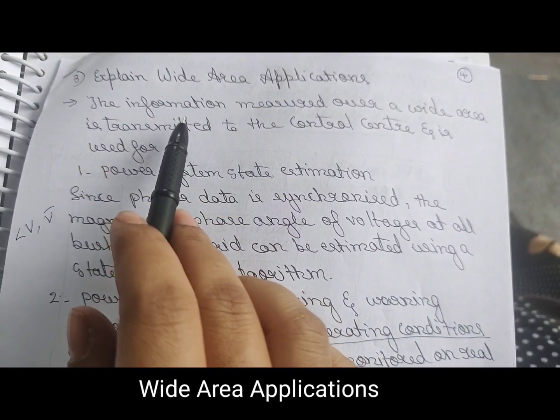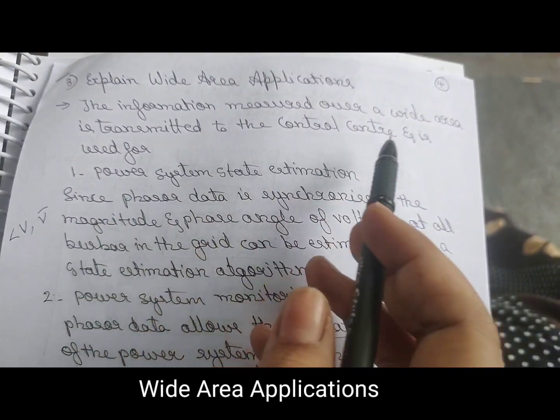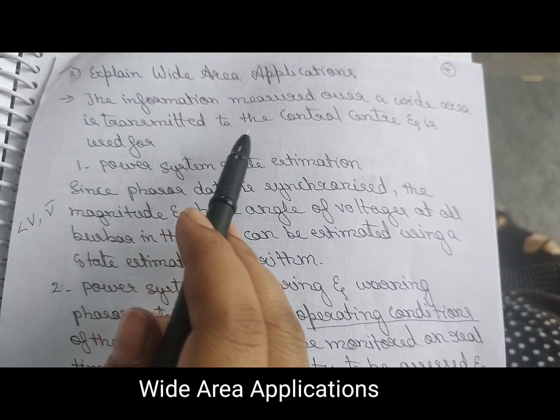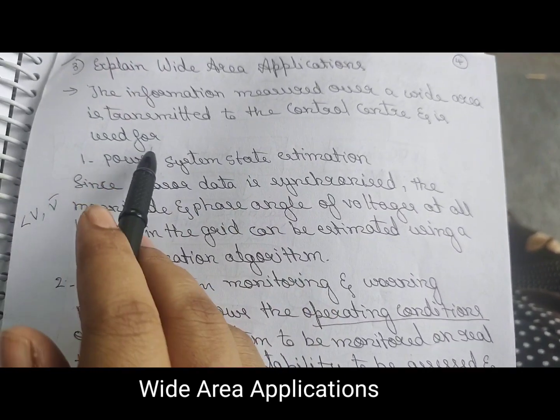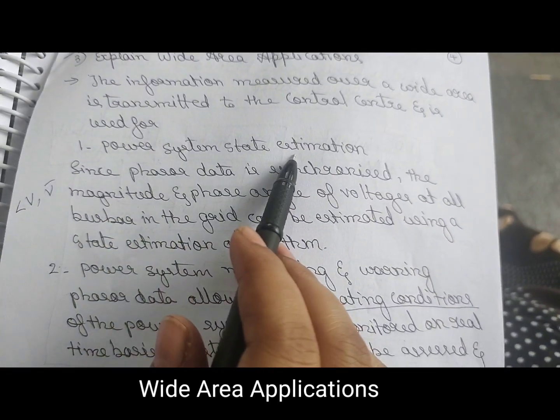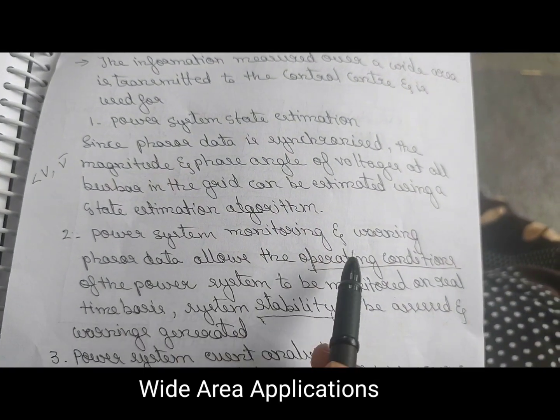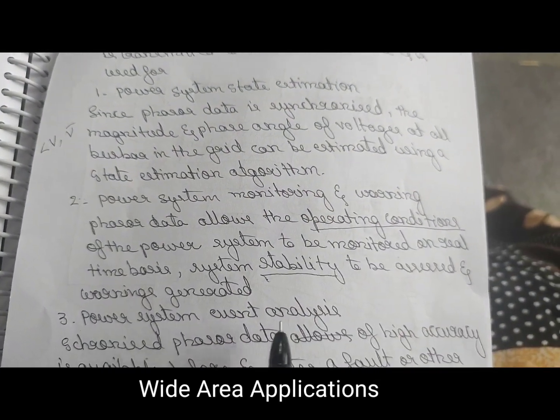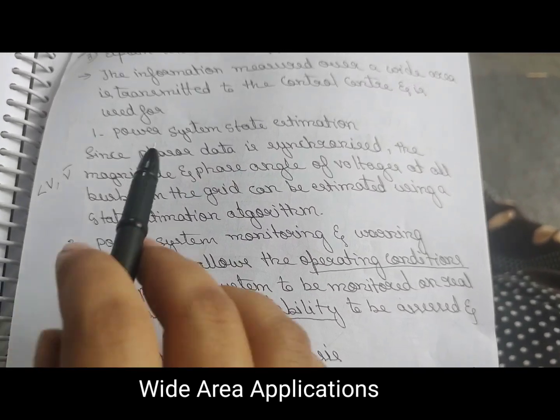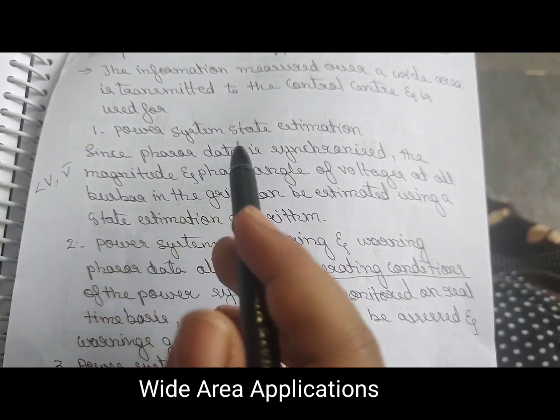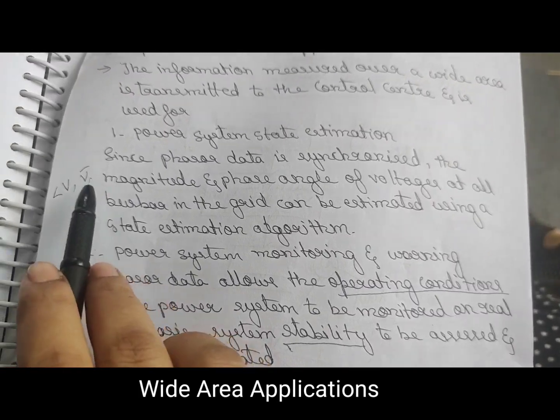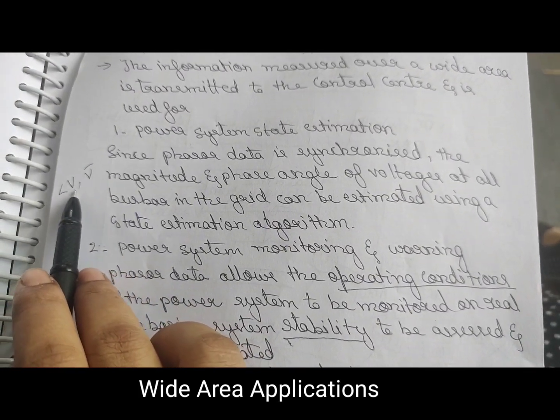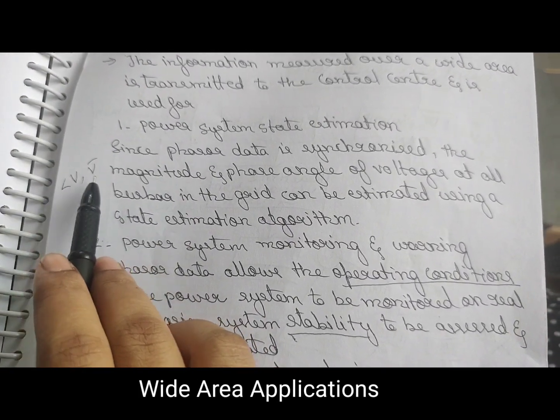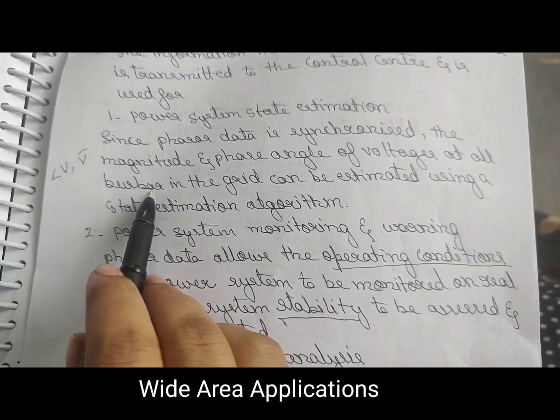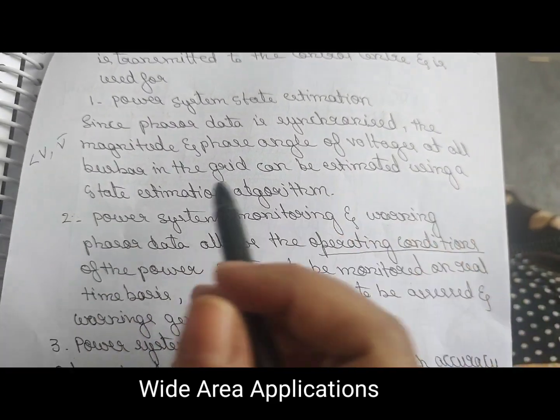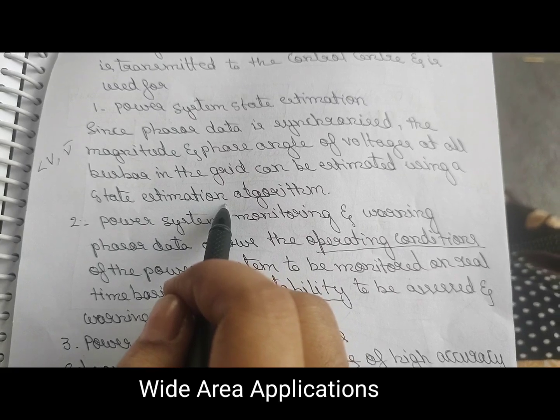In wide area applications, the information measured over a wide area is transmitted to the control center and is used for power system state estimation, power system monitoring and warning, and power system event analysis. In power system state estimation, whatever data is collected, the magnitude and angle of voltage at all bus bars in the grid can be estimated using a state estimation algorithm.